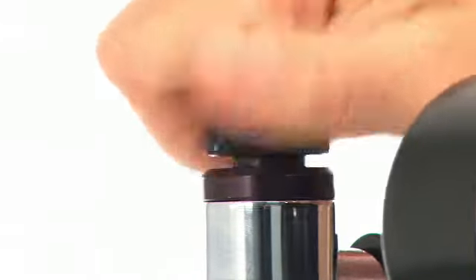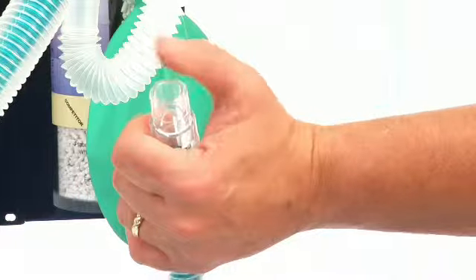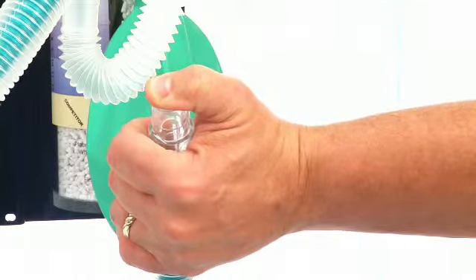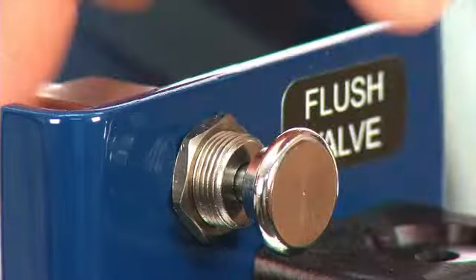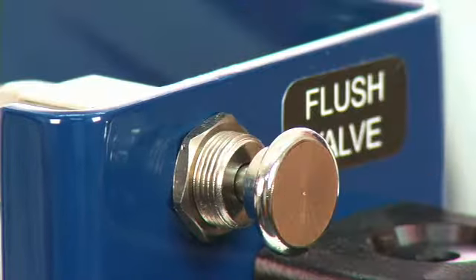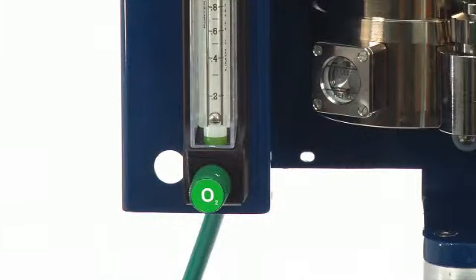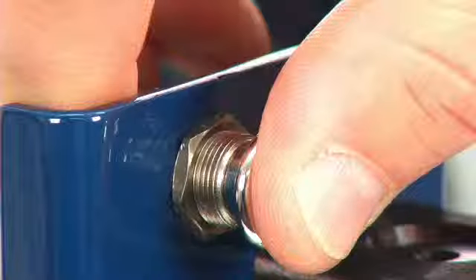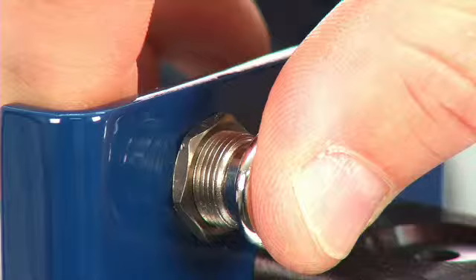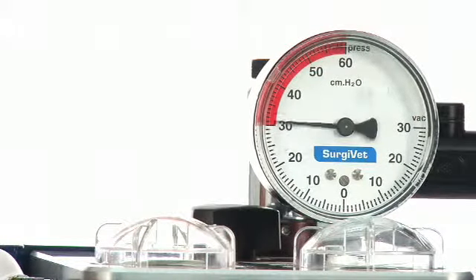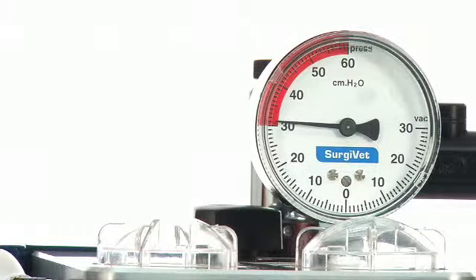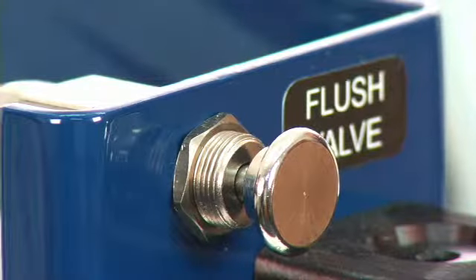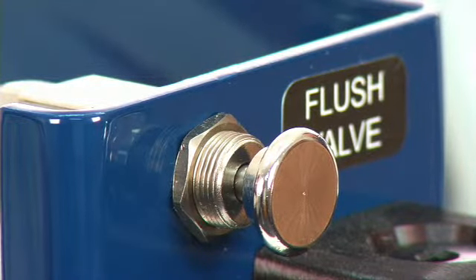Pressure test. Start by closing the pop-off valve, finger tight, without over-tightening. Occlude the patient circuit with your finger and fill the rebreathing bag by depressing the O2 flush valve. Do not turn on the flow meter during this test. Continue to depress the O2 flush valve until the pressure on the manometer reads 25 to 30 centimeters of water. Then release the flush valve button to discontinue flow.